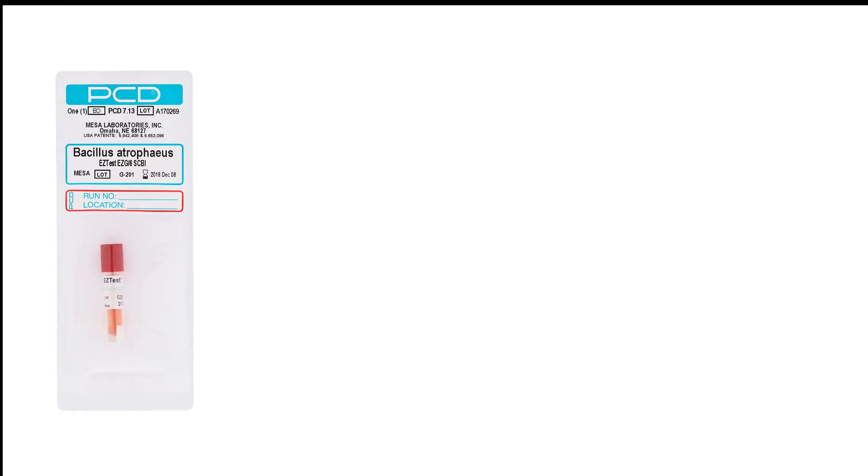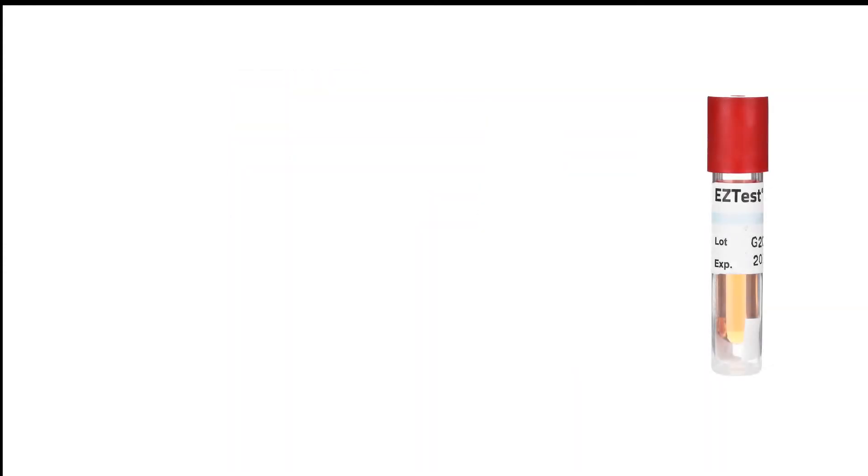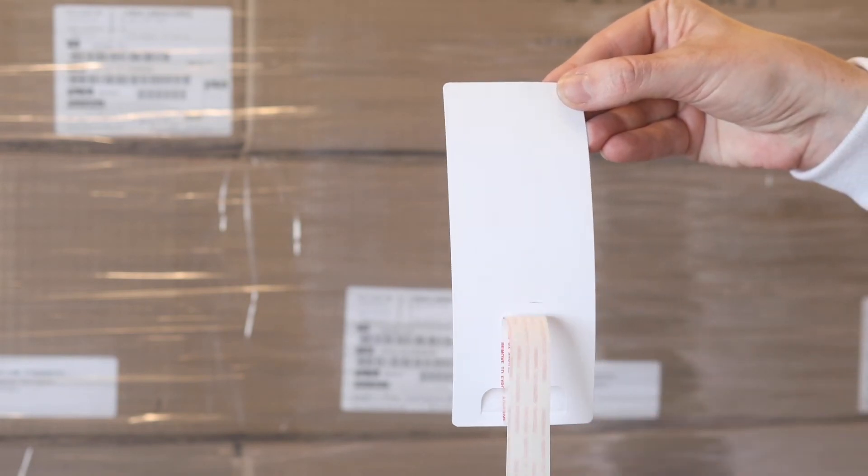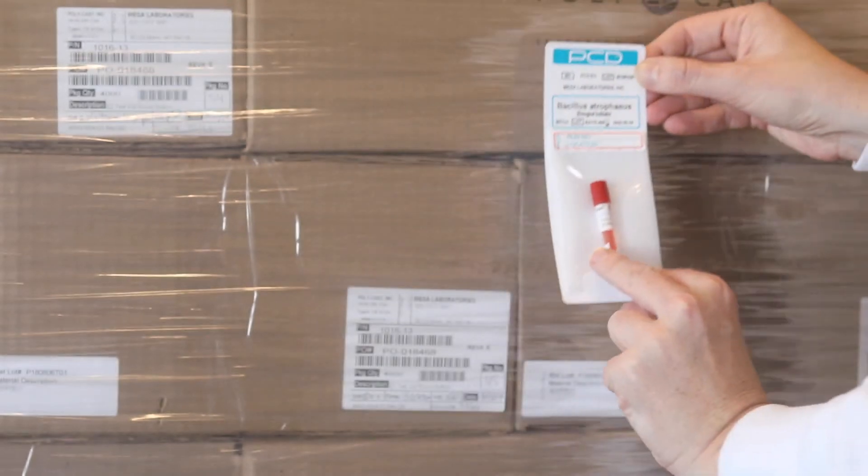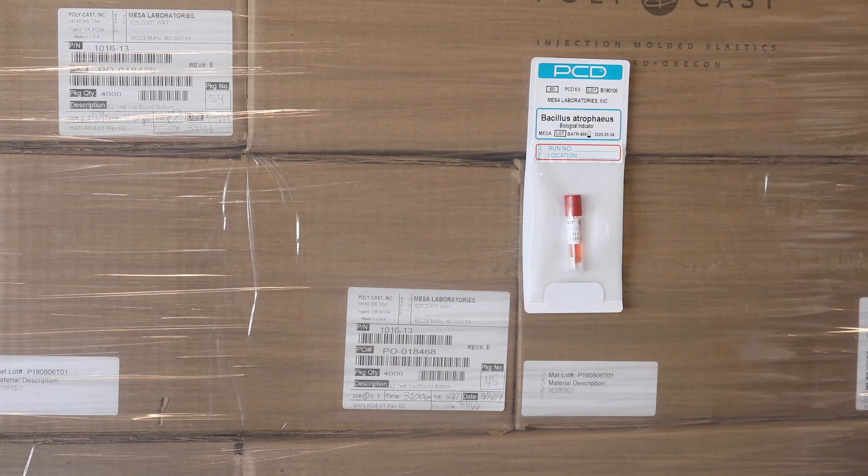For added efficiency, PCDs packaged with self-contained biological indicators enable users to see the results without waiting for multi-day incubation periods or sending the indicator to the lab for results. And because external PCDs can be retrieved from the outside of the load, they reduce exposure to harmful ETO gas and are less labor-intensive than homemade or traditional PCDs.